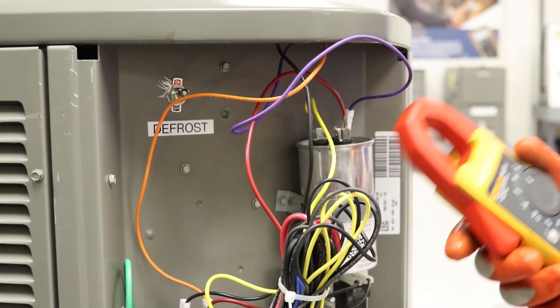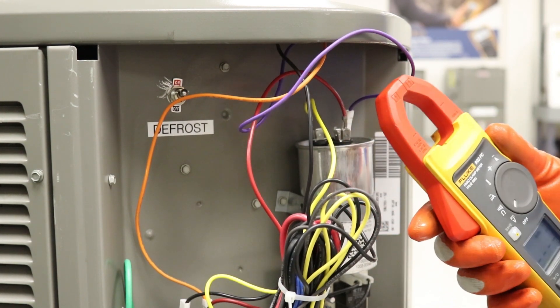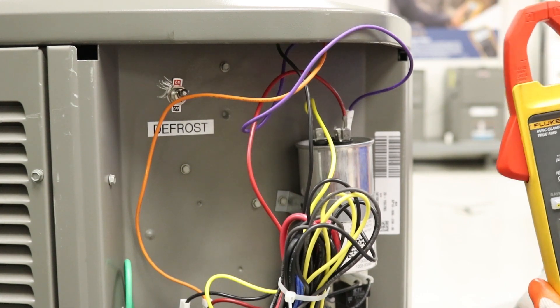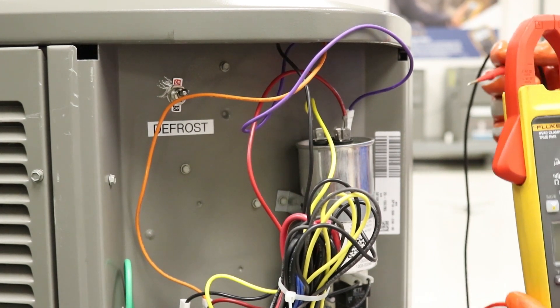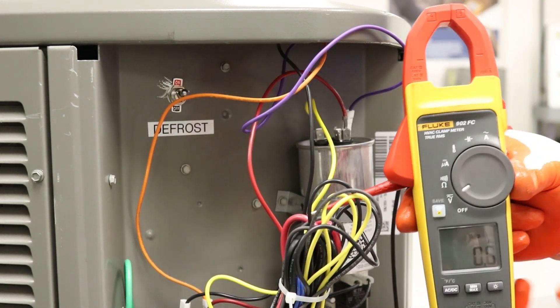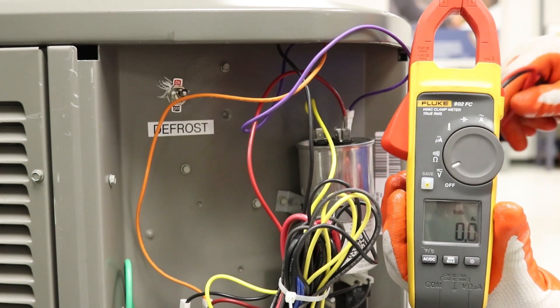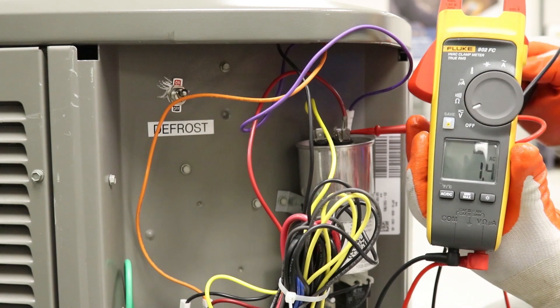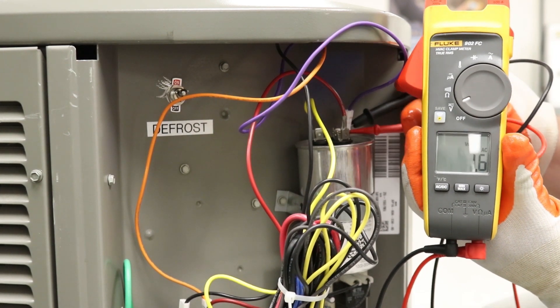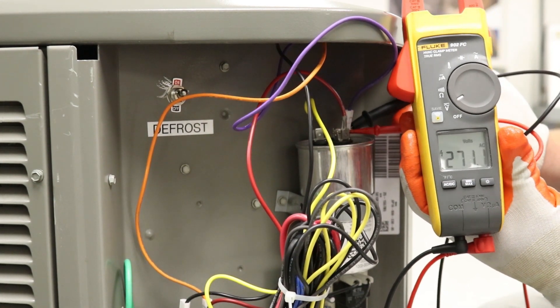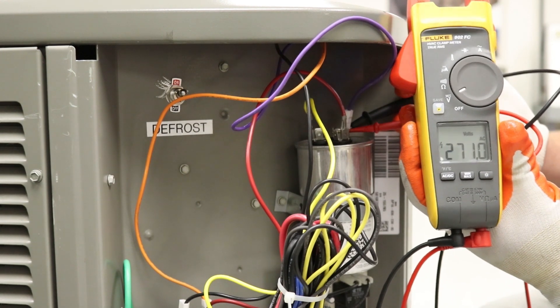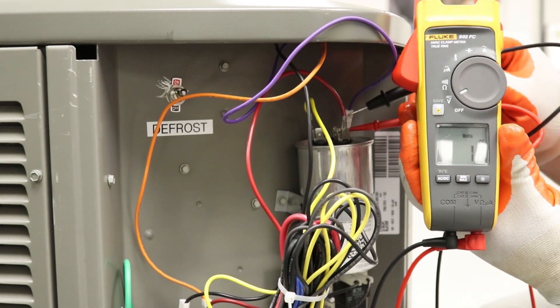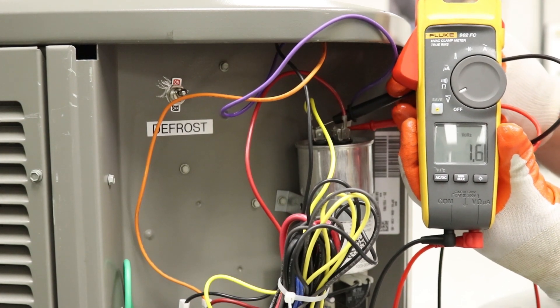From there, we're going to take our meter and switch it over to voltage. And we're going to check the voltage across both of those terminals to common. So we're going to start first with our fan terminal, which is reading 271.0 volts. Again, write that number down.